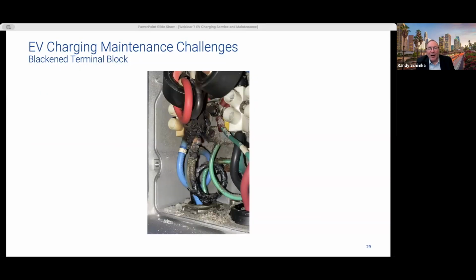Here we have a terminal block that's completely blackened, indicating either an overload or poor connections on the terminal block. So the black burning that you see suggests overheating from loose connections. Could be excessive current, I suppose, but that could lead to fires or even charger failure. So the lesson here is to use correctly rated terminal blocks and ensure tight, clean connections. You have to regularly inspect them for signs of any overheating, discoloration, etc. during maintenance.